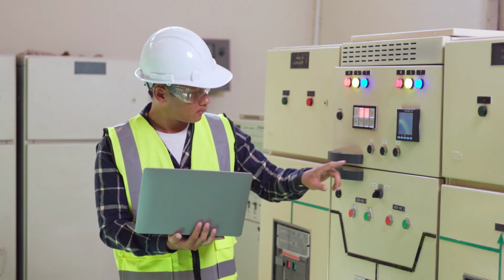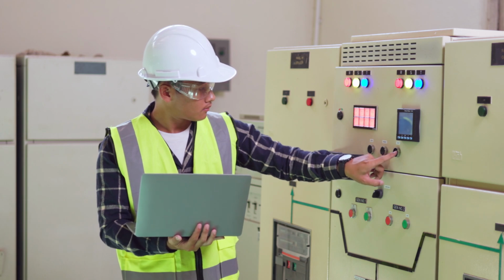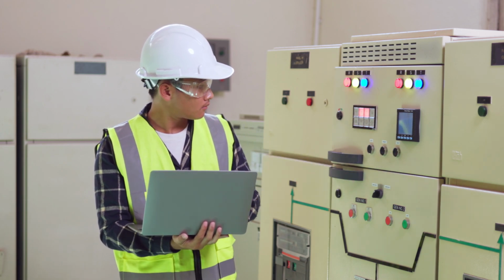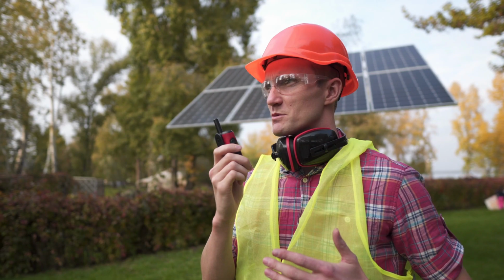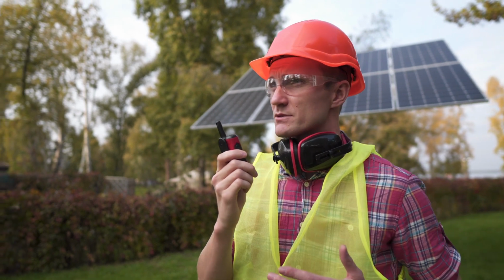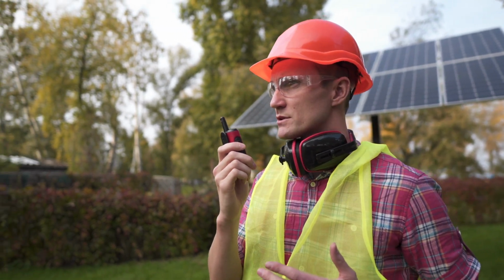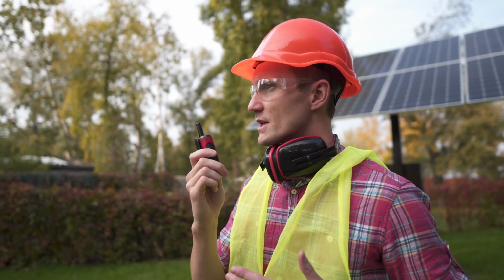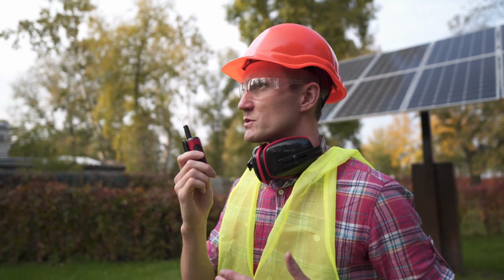polarity. We then advised the customer to correct the CT polarity and compare the readings again before turning the solar system back on. There is also another way to verify this issue through iSolarCloud.